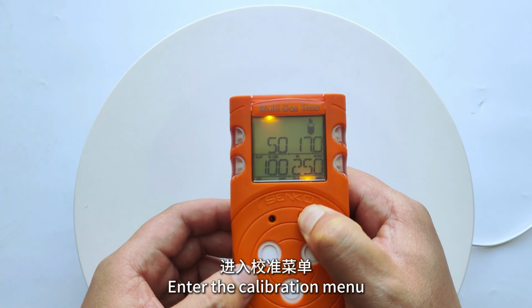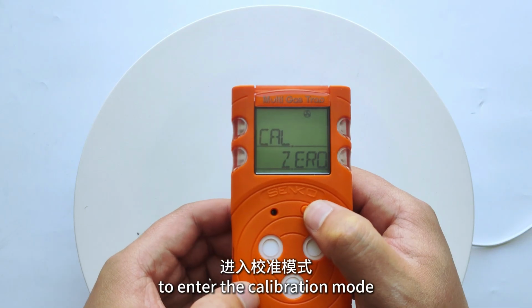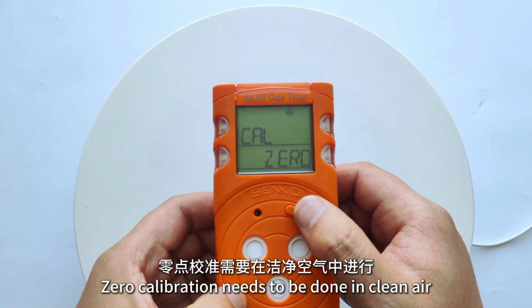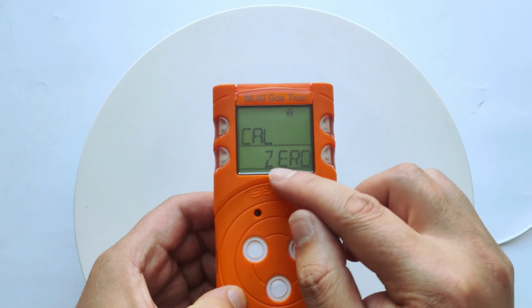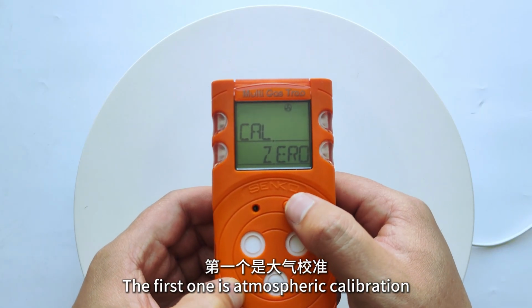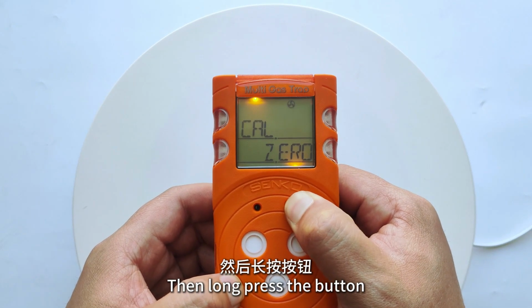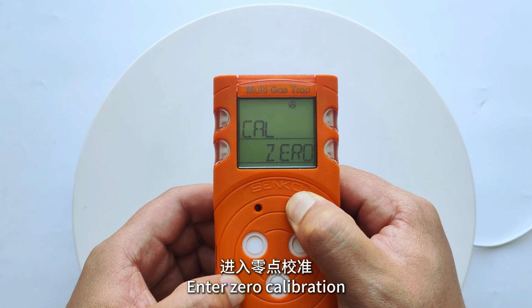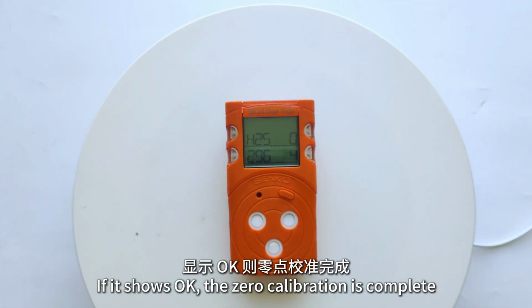Enter the calibration menu. Long press the button to enter the calibration mode. Zero calibration needs to be done in clean air. The first one is atmospheric calibration. Then, long press the button. Enter zero calibration. If it shows OK, the zero calibration is complete.